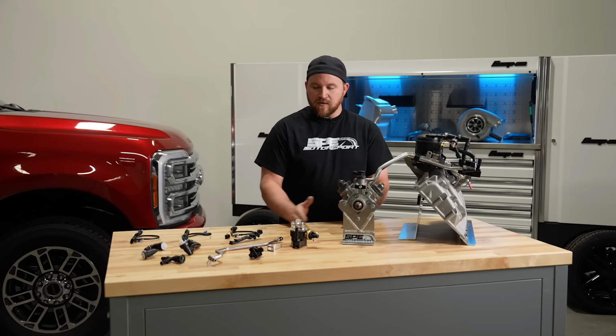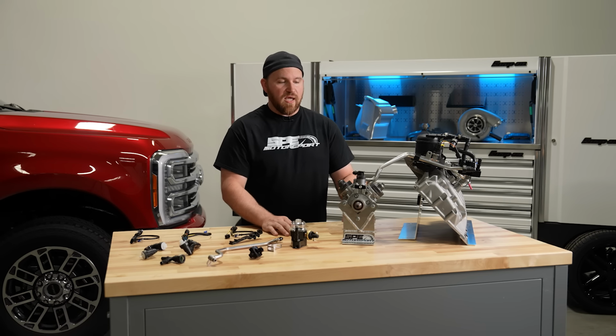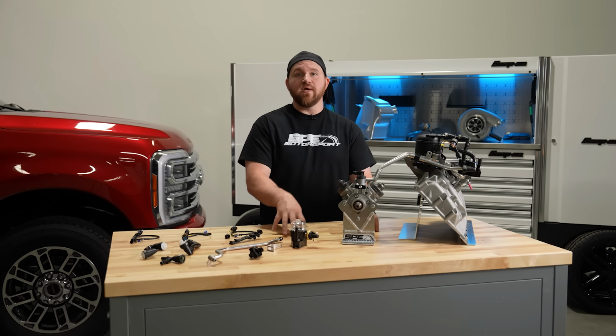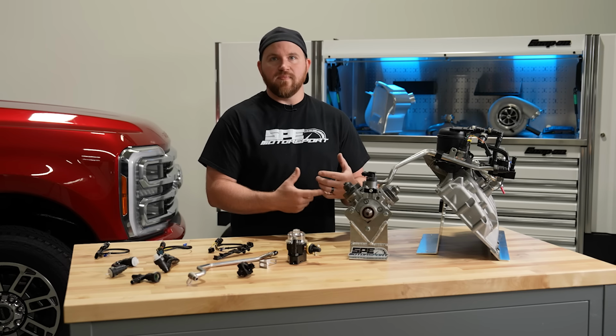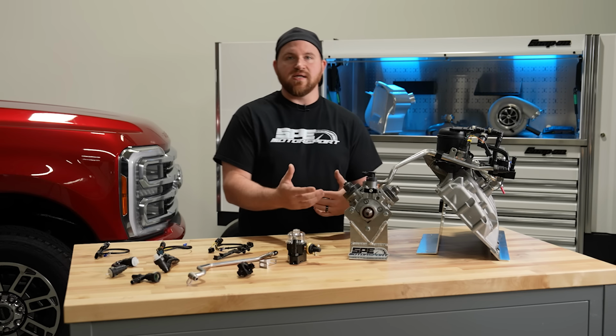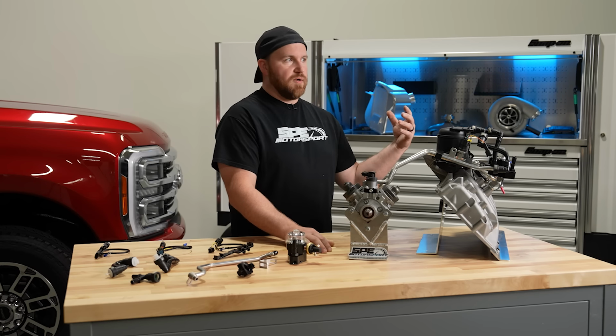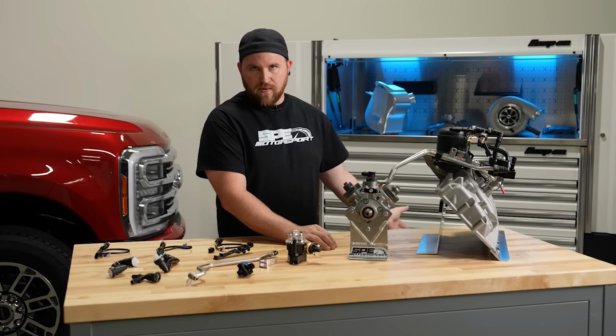A lot of our competitors that came out with a return filter after we did, they have a maintenance item now, because they use a cellulose filter in the return side of that system, and cellulose is essentially paper. If there's any kind of moisture in the fuel or anything, over time that filter is going to need to be changed, just as a filter would on a regular pickup in any scenario. Even if you don't have a failure, even if you're not running bad fuel, you always have to maintain those filters.